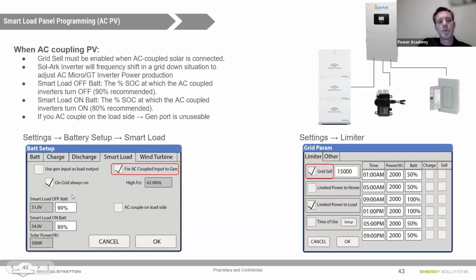So you do need to be able to shut that smart load off. Typically we'll set this at 90%. If you've got a big battery bank, you could probably take that safely up to 95%, but you want to make sure you're not pushing a lot of power into the batteries when those batteries are full. So that's the point of having this smart loads panel or the gen port shut off at 90% and allow it to drop down to 80% before it turns back on. That way the batteries will run for a little bit, discharge down to 80%, and then that solar will come back on and hopefully cover the home loads and continue to charge the batteries.